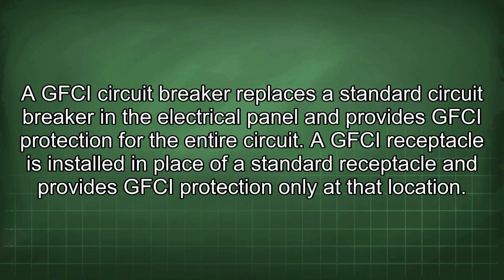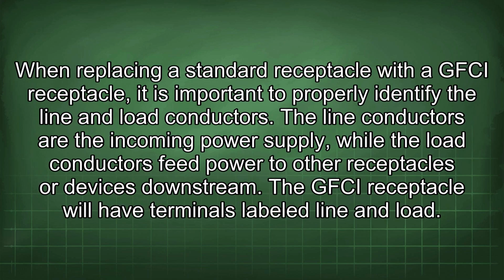A GFCI circuit breaker replaces a standard circuit breaker in the electrical panel and provides GFCI protection for the entire circuit. A GFCI receptacle is installed in place of a standard receptacle and provides GFCI protection only at that location. When replacing a standard receptacle with a GFCI receptacle, it is important to properly identify the line and load conductors. The line conductors are the incoming power supply, while the load conductors feed power to other receptacles or devices downstream. The GFCI receptacle will have terminals labeled line and load.